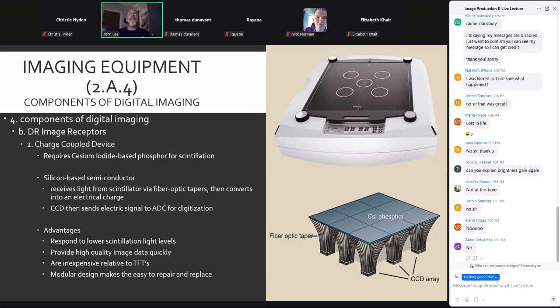Because of their small size, for an imaging system in radiography, we need an array of CCDs, which means we need multiple. In most cases, we would require 9 CCDs to make up and cover that 17 by 17 exposure area for these types of systems. So each CCD was responsible for taking its information from its little square here and putting it via fiber optic taper. That's what these little hairlines say. They take that large piece of real estate and minify it down to the CCD chip.